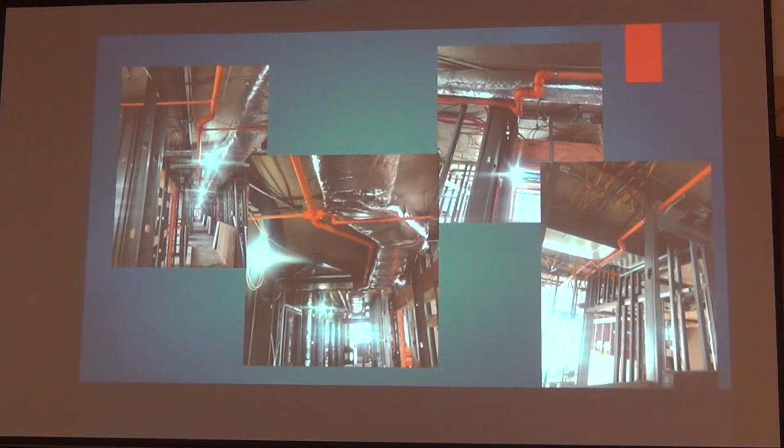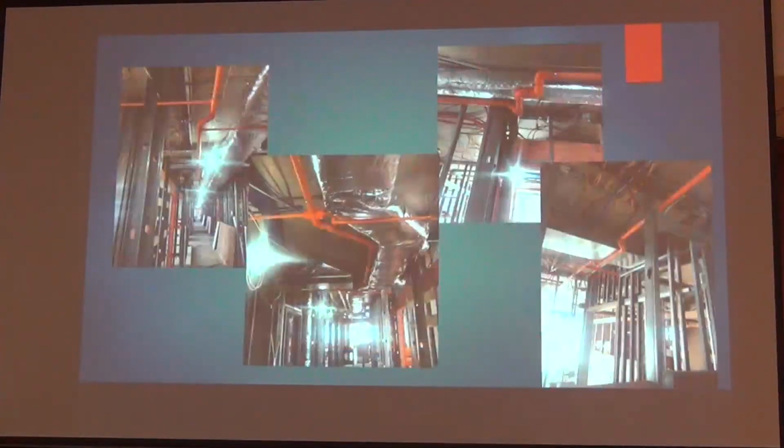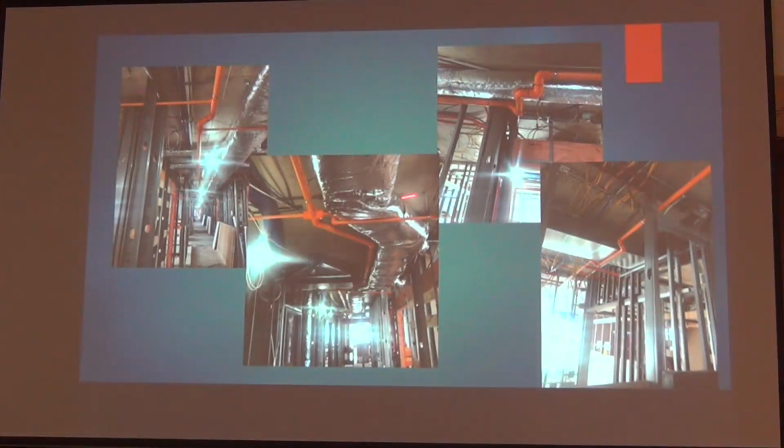So you see, oops, wrong button, come on. There we go. You can see you had to drop down and come back up. This is all on the same floor, and this is a 12-story building where every floor but the first two are the same like this. So I had to have new hydraulic calculations to make sure that we had enough flow. Yes, you can require that, because you are the end gap for making sure everybody stays safe and alive.